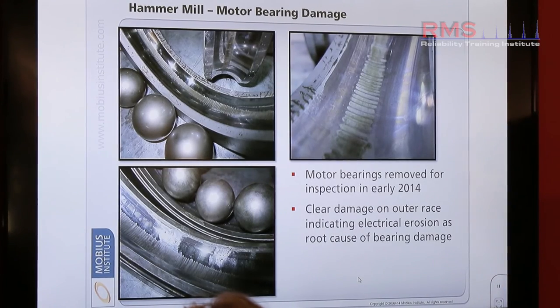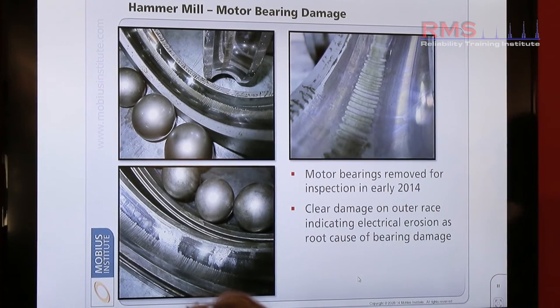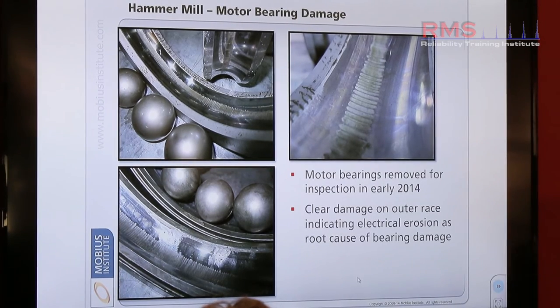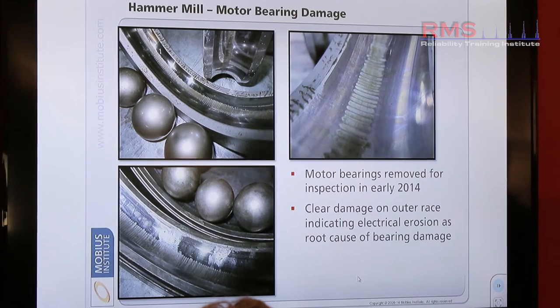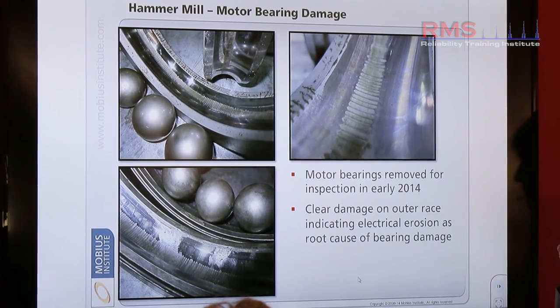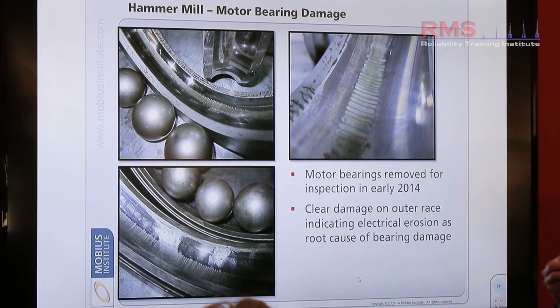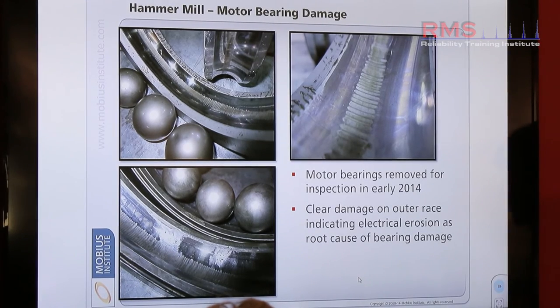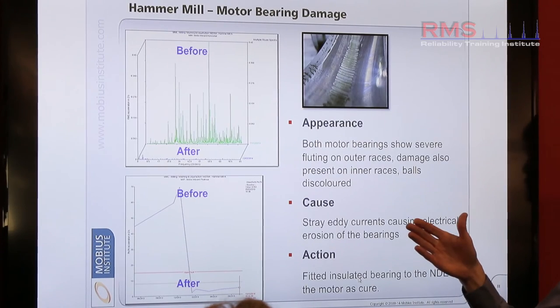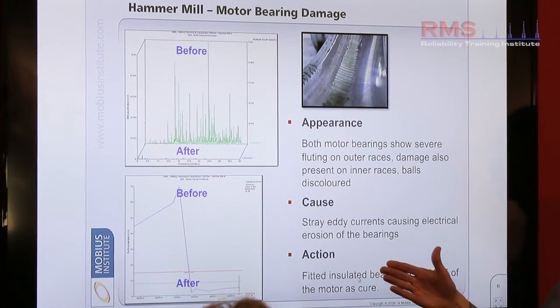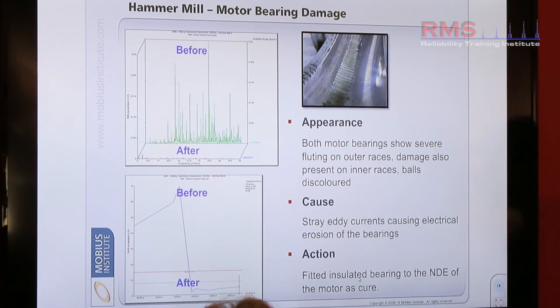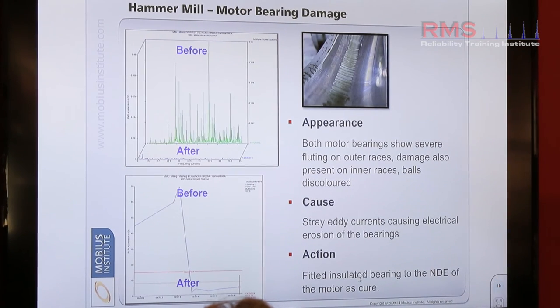So there's the actual bearing that was taken out. There's a very distinct wear pattern in this bearing, which provides the analyst with root cause information. But it's not just about detecting the fault. Condition monitoring only trends and tracks a defect. To improve the actual condition, to improve the reliability, we need to ask why — what caused it, and what action we're going to take — rather than just say put a new bearing in. What's caused it? Let's put that to bed as well as, obviously, install a new bearing.